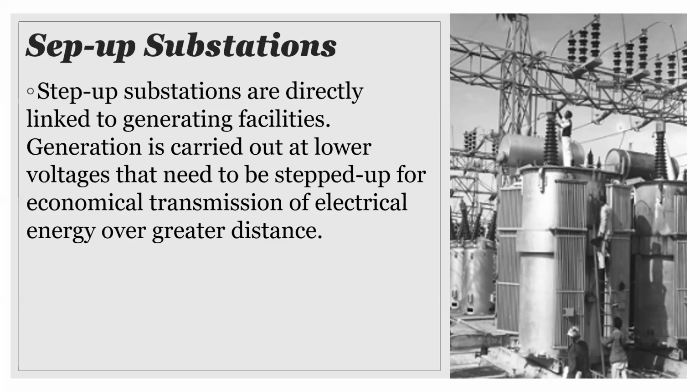All right. So your step up substations are directly linked to generating facilities. We know that here in Jamaica, our generation is coming at us at approximately 13.8 kilovolts. I have to be cautious with how I say this, but in terms of my own awareness of existing facilities, the highest generation voltage that I'm aware of is 24 kilovolts. If they have gone above that with increased technology for cooling, I am not aware, but for what I'm aware of, it's at 24 kilovolts. So that's what we are generating at maximum worldwide.